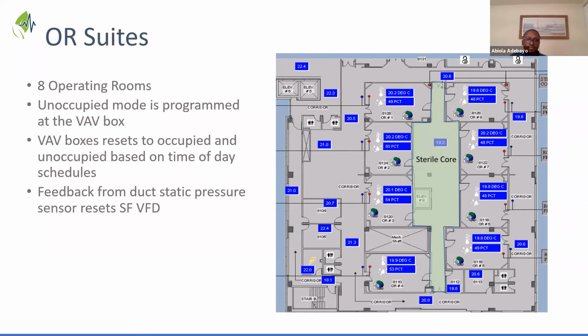Yeah, it was one of the concerns raised, and we had to clear that out during the testing phase, to see that the system can ramp up on time to achieve the 20 exchanges per hour when the building is occupied. Initially, we ensured that we had a 2 to 3 hour buffer to cover that. But over time, we're tweaking the hours. Currently we're at 2 hours, so the system is running 2 hours before occupancy. I think there's still room for improvement on that.